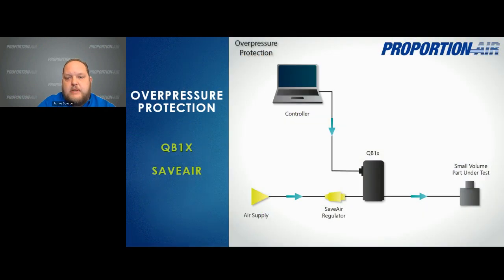Shifting gears just a little bit, our next application is overpressure protection. Overpressure can be a concern when working in sensitive applications. Applications that require precise pressure regulation to fill small volumes benefit from an additional regulator that controls the supply air before it reaches the electro-pneumatic pressure regulator. This is especially true when you're dealing with inches of water column or other small values.